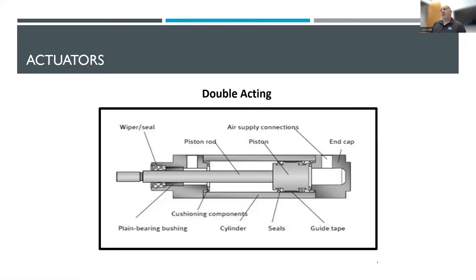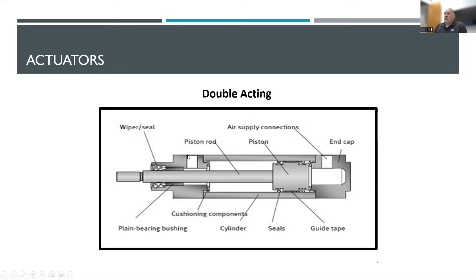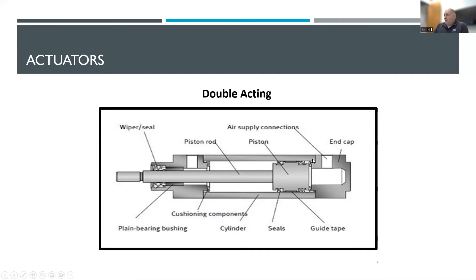In some instances we don't want a spring return — we want a powered return. Maybe we're not only pushing something but need to pull it back as well, or if you have a heavy diverter gate that requires pressure to bring it back. In that case we have air applied to both sides, so it's powered both ways, and you exhaust to the other side. There are some applications where you can power it partway and then pressurize both sides to hold it in place, though multi-position control with pneumatics does typically get more expensive, to the point where you might look at an electric actuator.